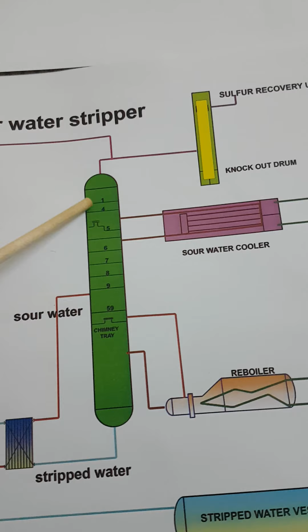And here we maintain temperature with the help of steam. There will be a continuous supply of steam in the reboiler, and we maintain the pressure of steam. For medium pressure steam, there should be about 3.5 to 4 kg, and for high pressure steam it will be more than 12 kg per centimeter square gauge. So this was about the temperature and pressure parameters, and how we maintain them.